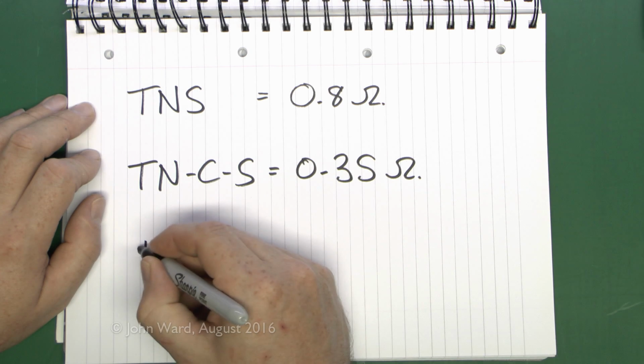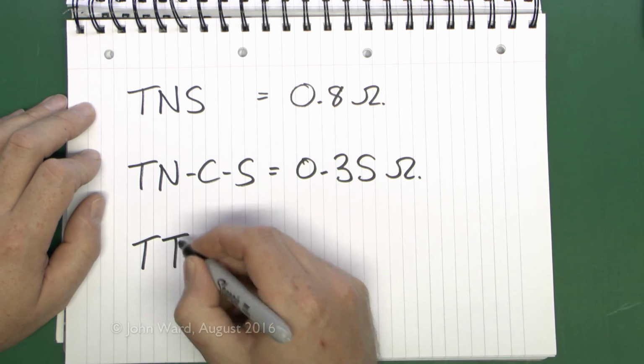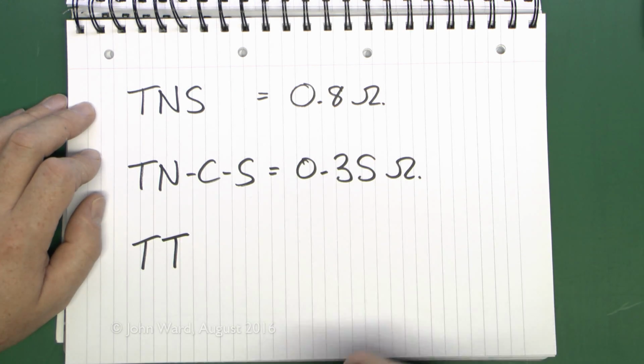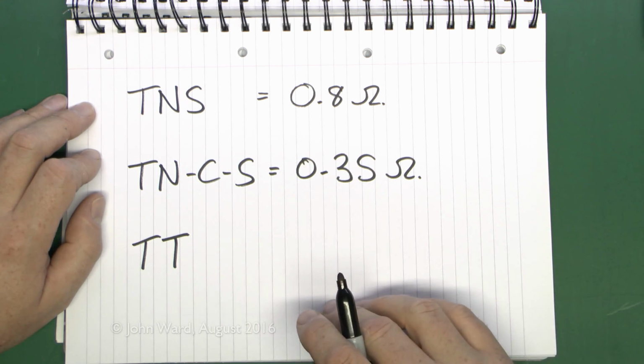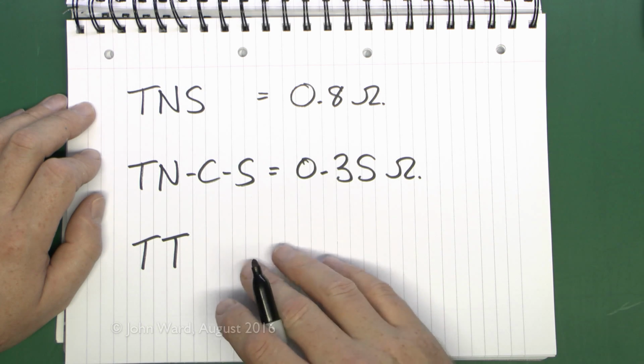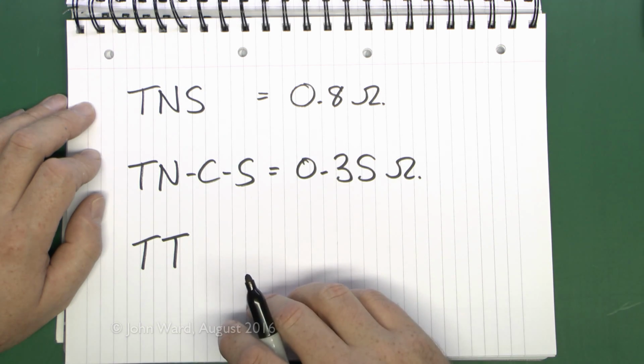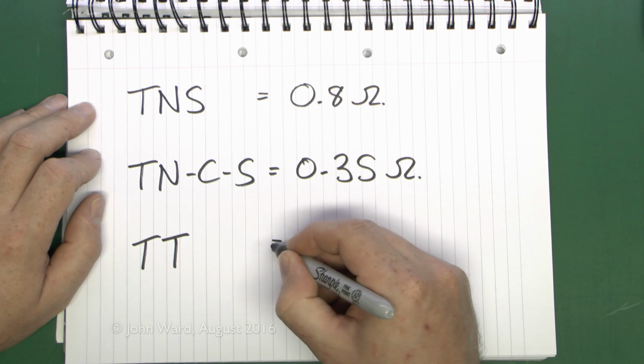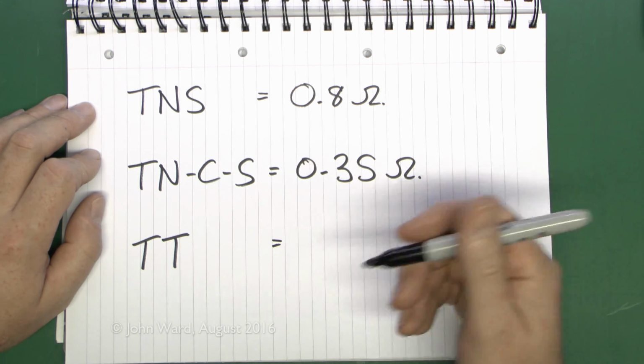And the third system, which is somewhat less common, is the TT system. This is where you don't actually have an earth connection directly back to the transformer. It relies on an earth electrode in the ground, so the return path in that case is actually through the general mass of the ground. And in this case, the resistance can be anything up to 100 ohms or more.